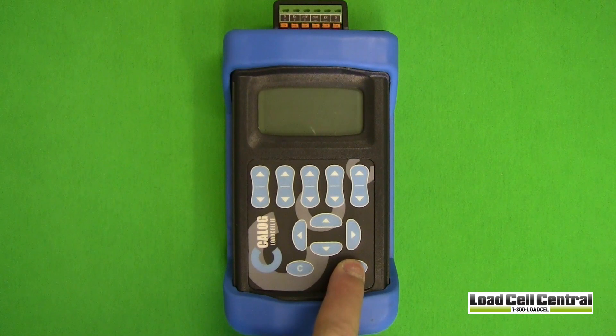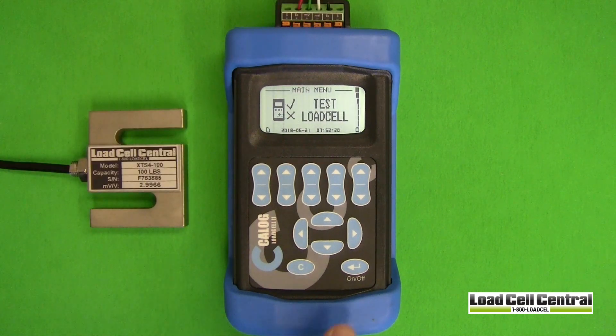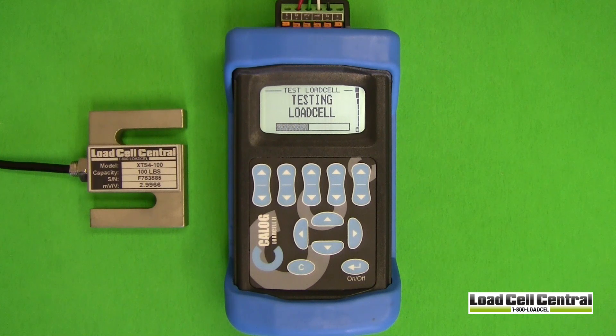Testing a load cell is very simple. Using the documentation provided with my load cell and Calog LC2, I have attached this S-Type load cell, our XTS4, to the unit. Once connected, I can begin the load cell test. After 30 seconds, the results are displayed. By comparing these values to the specifications listed on my load cell certificate, I can determine that this load cell is in good working order.